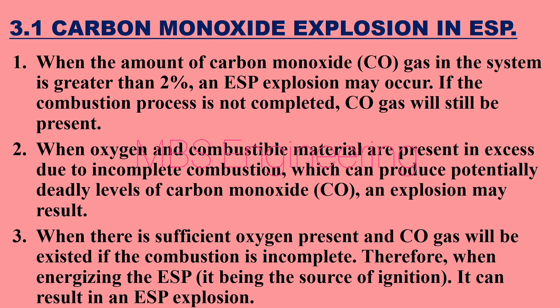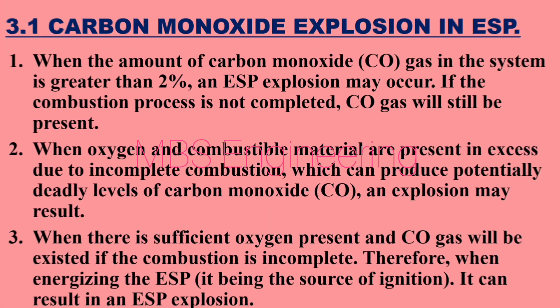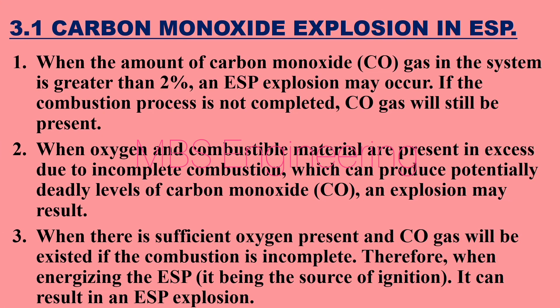Point 3: When there is sufficient oxygen present, CO gas will exist if combustion is incomplete. Therefore, when energizing the ESP — it being the source of ignition — it can result in an ESP explosion.